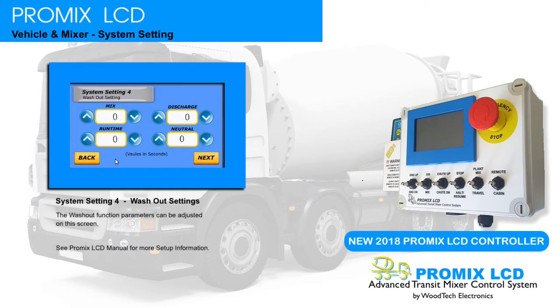System Setting 4, Washout Setting. The washout function parameters can be adjusted on this screen. Mix is the time, in seconds, the mixer will spend in the mixing direction on each part of the cycle. Discharge is the time, in seconds, the mixer will spend in the discharging direction on each part of the cycle. Neutral is the time, in seconds, the mixer will spend in the stop state as the process transfers from the mix to discharge direction and vice versa. Runtime is the total programmed runtime of the function, in seconds. At the completion of the total time the system will return to the stop state.